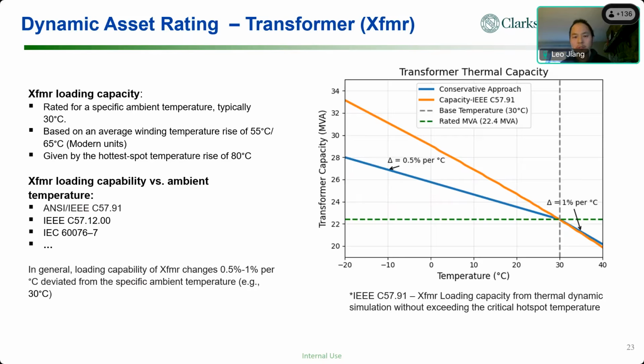In the IEEE standard, there are some recommendations. One recommendation is that you don't really need to run the thermodynamics to see, if your ambient temperature is, for example, 10 Celsius, how that would increase the thermal capacity of your transformers. If you look at the figures here, the blue line is a conservative estimate of the thermal capacity of transformers following the IEEE standard. Indeed, this blue line is even more conservative than the recommended conservative practice. So what it says, the blue line, is that if your 24 hours average ambient temperature is below 30 C, you gain 0.5% of your capacity per degree of decreased ambient temperature.